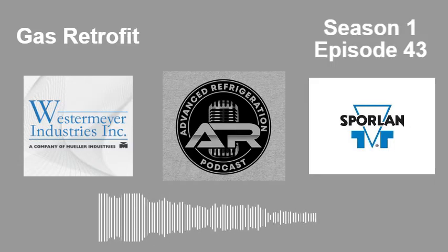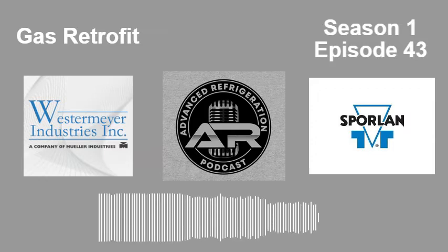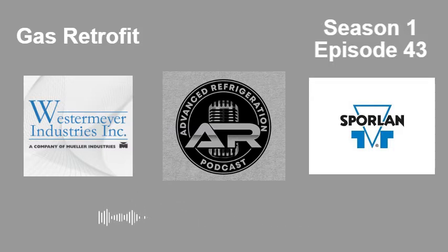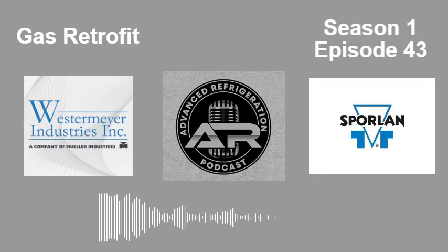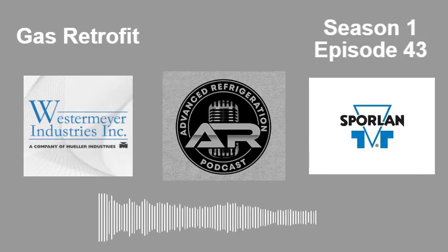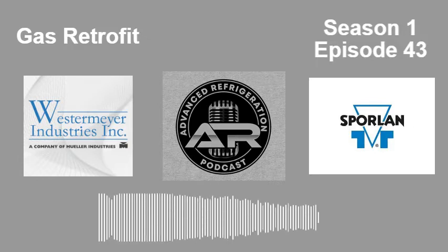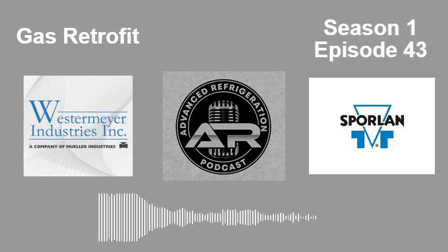Sporlan also makes a retrofit guide for every one of their valves with O-ring part numbers on it. So a lot of times I'm not ordering a liquid differential valve rebuild kit when I could order 2 O-rings that are $10 versus a rebuild kit that's $500. I'll have Brett put that up when he posts it - every single seal in every valve Sporlan makes is listed, whether it's a kit or individual parts. I don't know what Danfoss has, but since every seal is listed, it makes it easier to identify stuff.